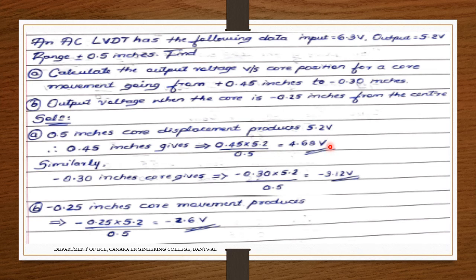But we have to see in the negative range also, because they mentioned plus 0.45 to minus 0.30. For minus 0.30 inches core, same thing: instead of 0.45, we write minus 0.30 into 5.2 divided by 0.5, which equals minus 3.12 volts. We just have to understand the reference given and calculate for the given value, 0.45 to minus 0.30. Since the range is from plus 0.5 to minus 0.5, it will lie within this: the upper limit is 6.3, so 4.68 is within it, and here minus 3.12.